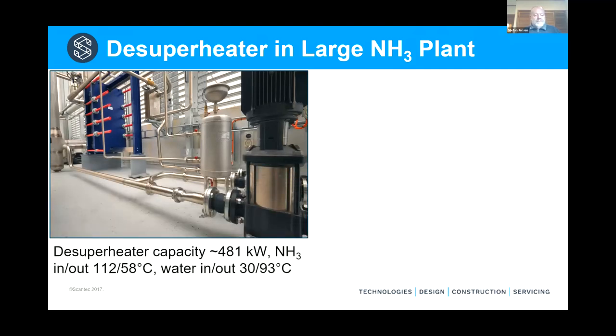the desuperheater is of the plate type, and you can see both heat exchangers here. The blue one is the ammonia-water heat exchanger. And the other one next to it, that little water-to-water heat exchanger, is the one I showed in the previous diagram. This is to create a closed water loop for the desuperheater itself, so we avoid that it fouls up. The pump in the foreground is the pump that circulates the water through the closed circuit.